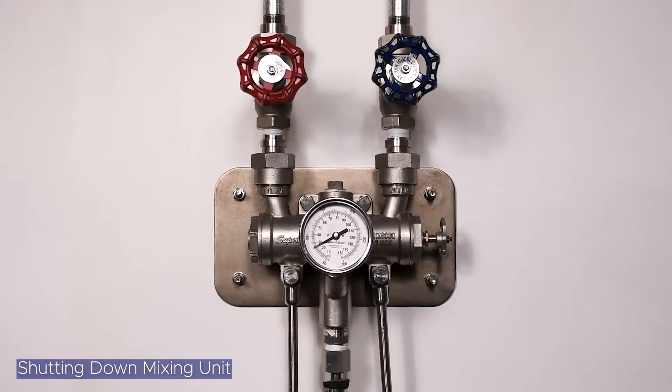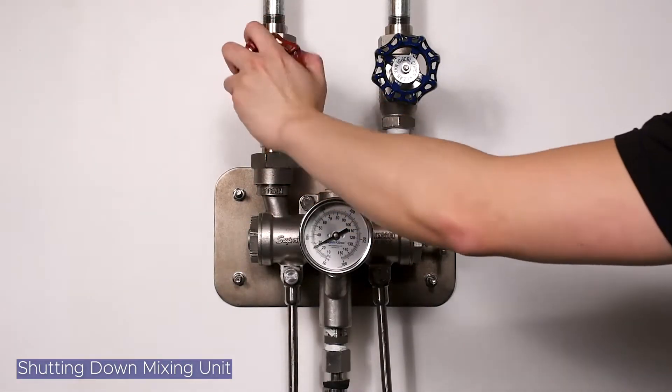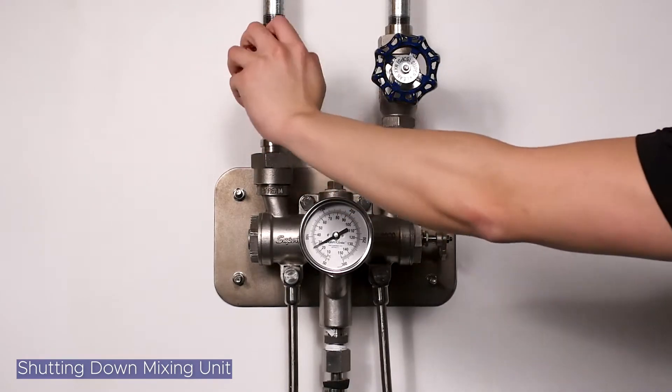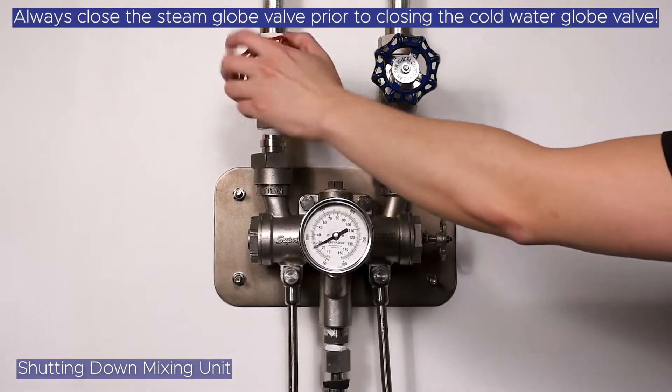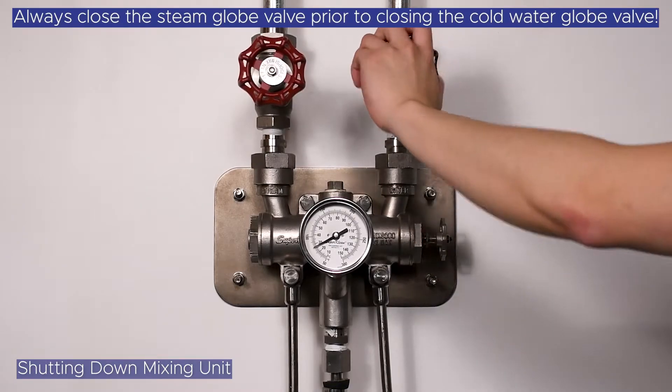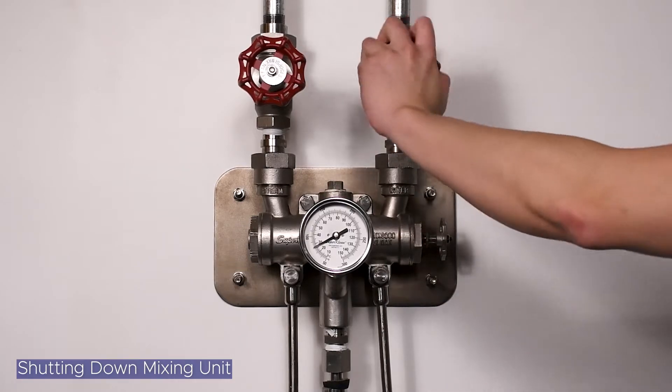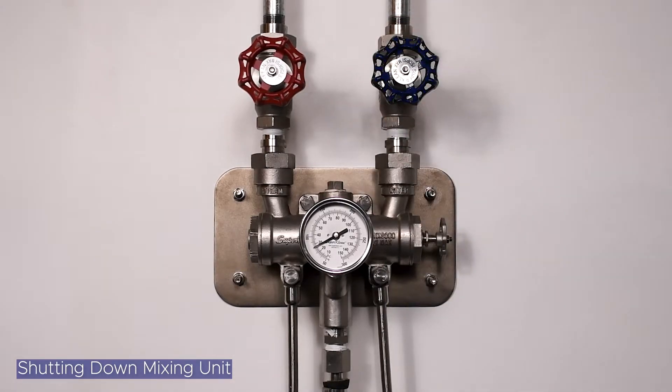To shut down your mixing unit, close the steam valve by turning the red globe valve clockwise until it is fully closed. The steam valve should always be closed before the cold water valve. Next, close the cold water valve by turning the blue globe valve clockwise until it is fully closed.